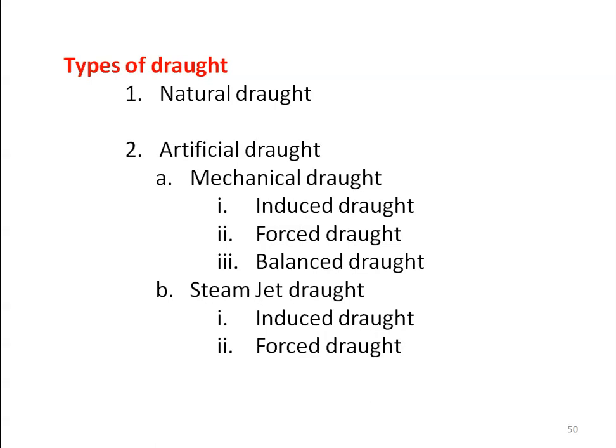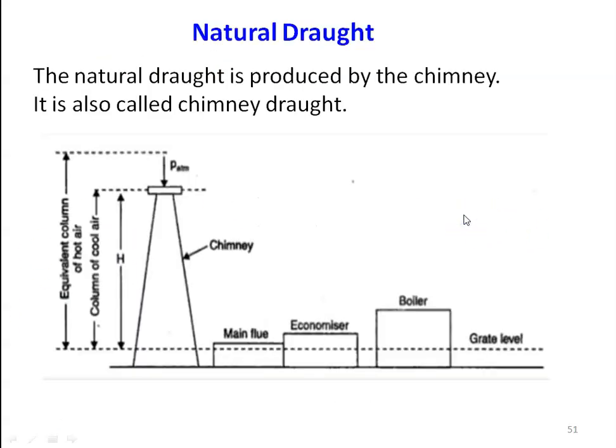We will study the construction arrangement for various types of draughts and their relative advantages. First, natural draught. Natural draught is produced by the chimney — it is also called chimney draught. Looking at the arrangement of the various boiler parts and the chimney, we have the grate level, where burning of the fuel takes place. Air flows through the boiler, economizer, and the main flow passage and then to the chimney. There is a pressure difference between the atmosphere and the column of hot gases inside the chimney, and the flow of gas is created by this temperature difference.